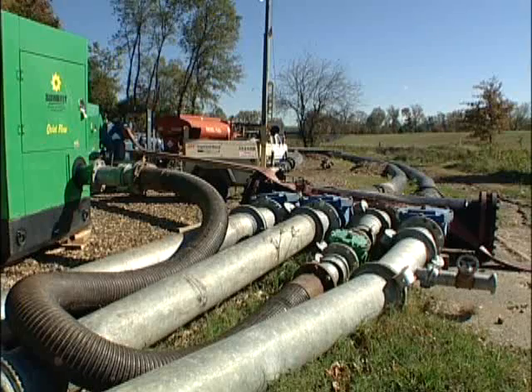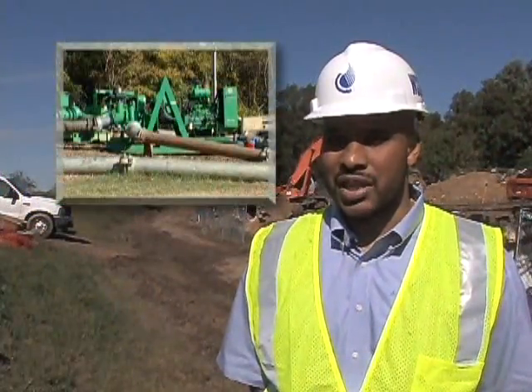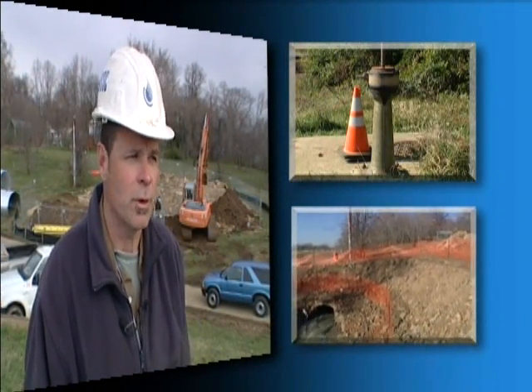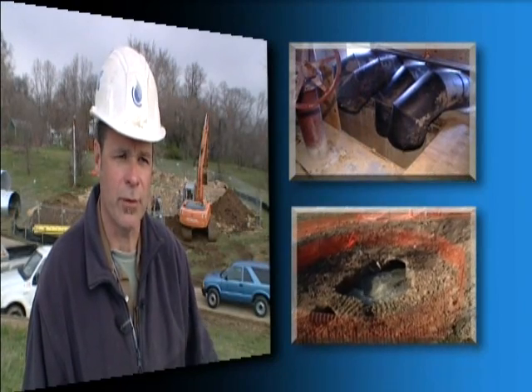The design and implementation of a fail-safe bypass was now crucial. The major challenge up front was to stop the line, set the bypass, and route the flow around the collapse. We had no place to discharge except 2,000 feet downstream. The idea was to bypass from one of our sluice gates — a gate that controls the flow of the sewer — and then pump it from there to the junction chamber, which dumps into the 96-inch sewer main.